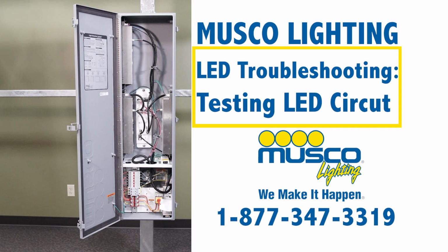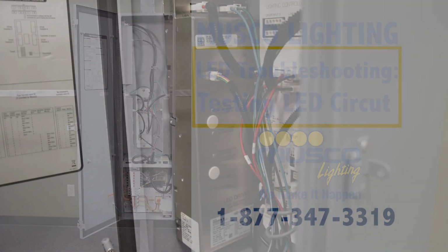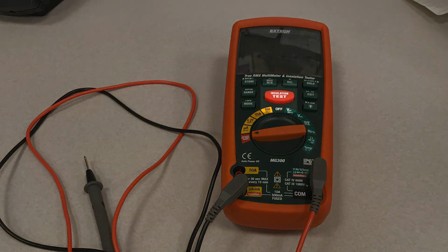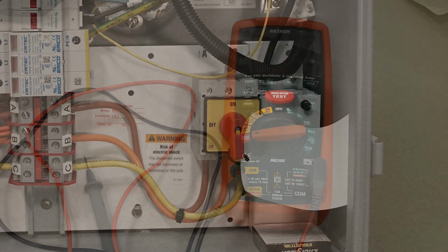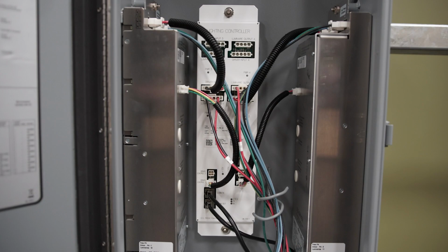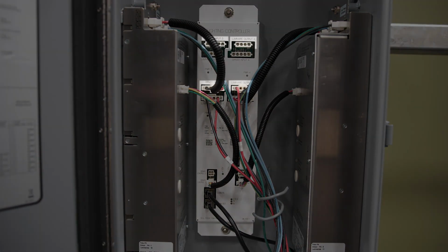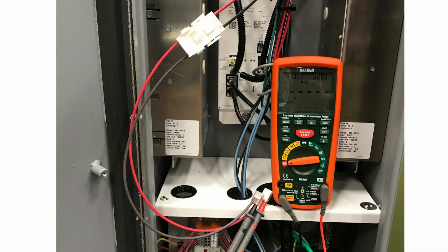The first test will be on a driver known to be good in order to set a baseline reading for your meter. Set your meter to insulation test and set the range to 1000 volts. Turn the disconnect off, wait 45 seconds after turning it off to let the driver completely power down. If your enclosure has a controller board, remove the 5-pin connector from the slot in the controller board labeled Luminaire Output and install the 5-pin MUSCO test harness to the output harness.